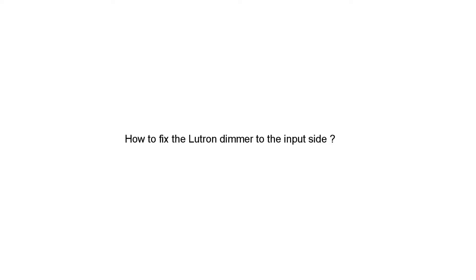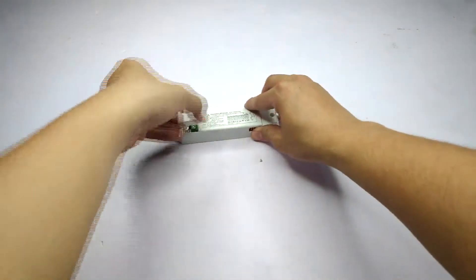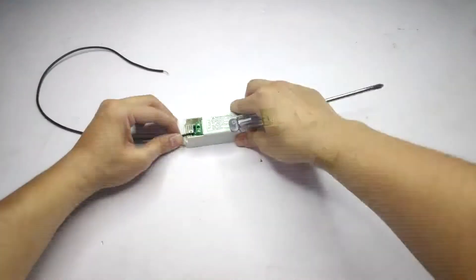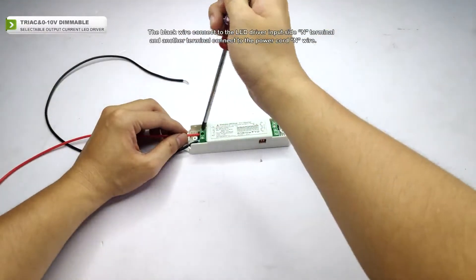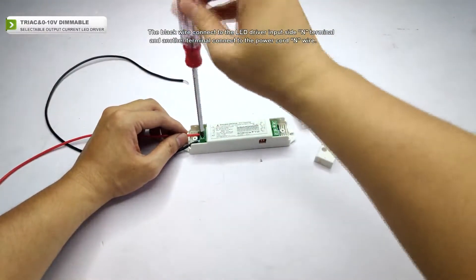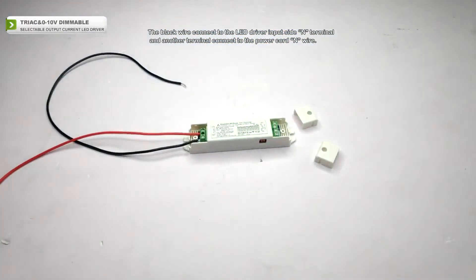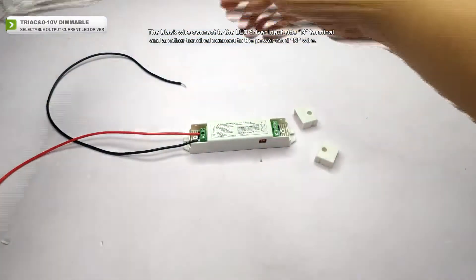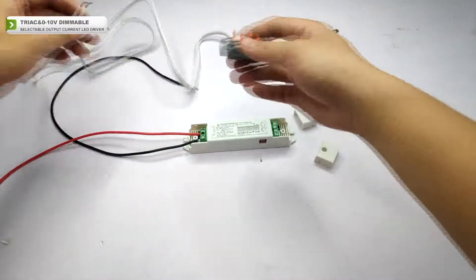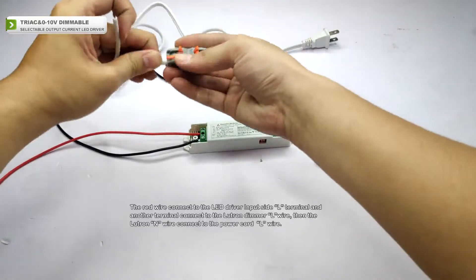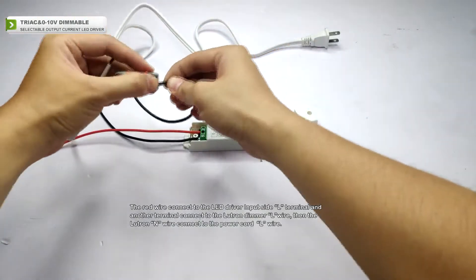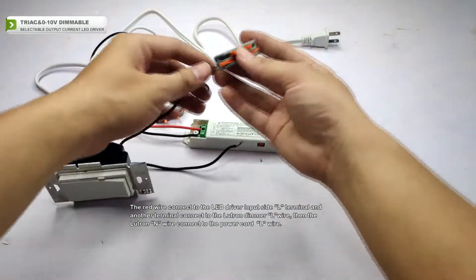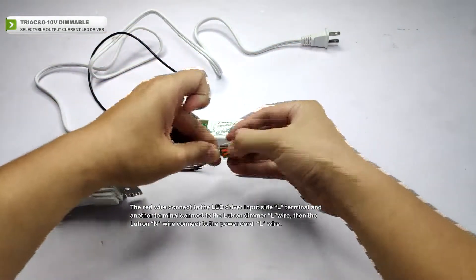To fix the Lutron dimmer to the input side: the black wire is connected to the LED driver input side N terminal, and another terminal connected to the power cord. The red wire is connected to the LED driver input side L terminal, and another terminal connected to the Lutron dimmer L wire.